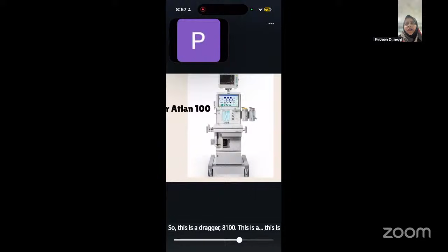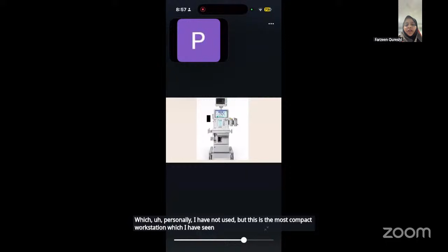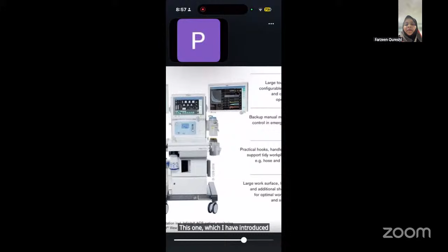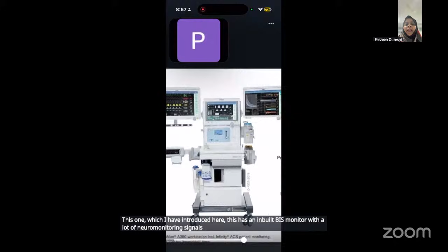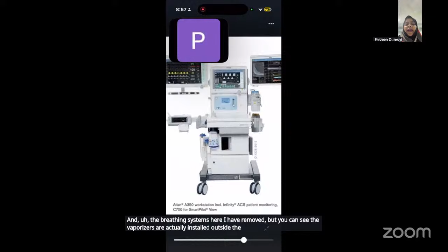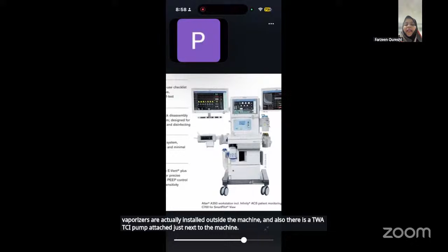So this is a Draeger Atlan 100. This is a 4-year-old model of Draeger, which personally I have not used, but this is the most compact workstation which I have seen. Otherwise, the workstations are quite bulky. This one, which I have introduced here, has an inbuilt BIS monitor with a lot of neuromonitoring signals, including SSEP and MEP in the same machine. And the breathing systems here I have removed, but you can see the vaporizers are actually installed outside the machine. And also there is a TIVA TCI pump attached just next to the machine. So that's a real big advancement, that you have all in one machine. This workstation is definitely what the name says, Infinity.